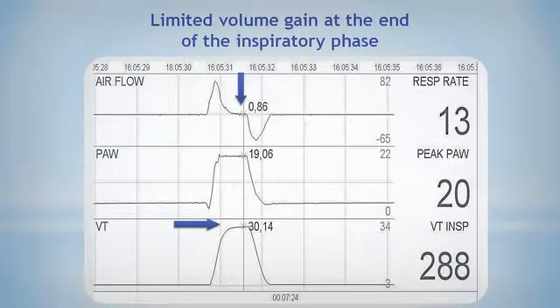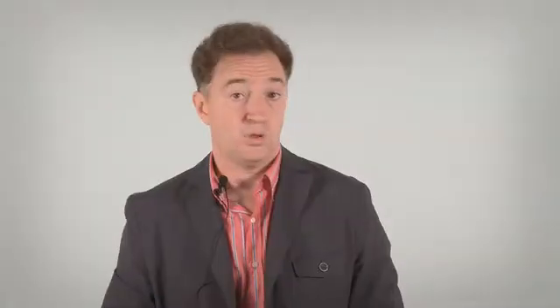However, we must consider that if we have selected a long cycling criterion, we are operating in the final portion of the flow-time curve. In this situation, the volume gain from prolonging inspiratory time may be really low.